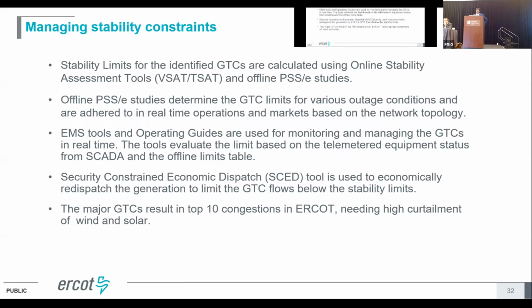And we have to come up with different limits for different predetermined outage conditions. All of those outage conditions are modeled in our EMS system, and the EMS system looks at the current topology in the SCADA. The SCADA standard is every 4 to 10 seconds, so it determines the topology every 4 to 10 seconds, and based on the predetermined limits, it tells the operator exactly what the limit is for this outage condition. So if there is a forced outage, we immediately have the limit updated based on this offline analysis, and then the operator will be able to maintain the flow. They can run a security constraint economic dispatch to redispatch the generation to manage the flow.